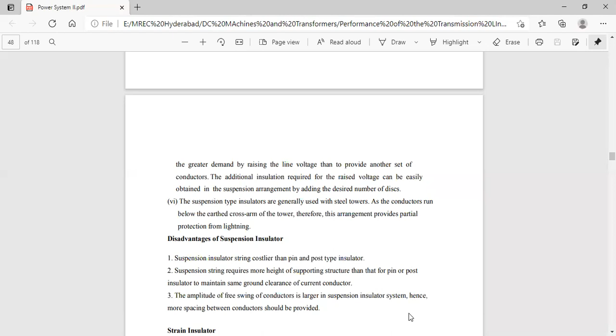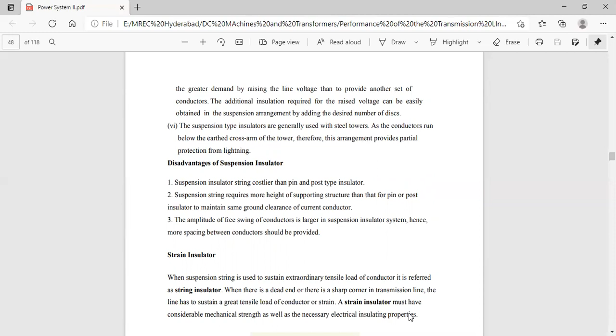The suspension insulator strings are costlier than pin and post type insulators. Suspension strings require more height of supporting structures than that for pin or post insulators to maintain the same ground clearance of the current conductor. The third one is that the amplitude of free swing of conductors is larger in the suspension insulator system. Hence, more spacing between the conductors should be provided. So these are the disadvantages of the suspension type insulators.